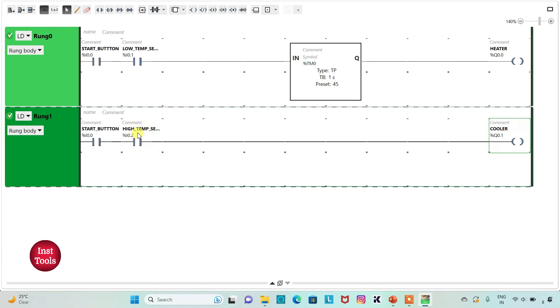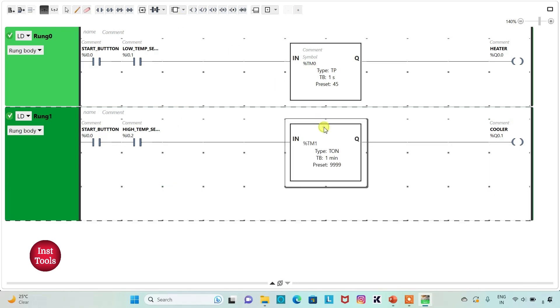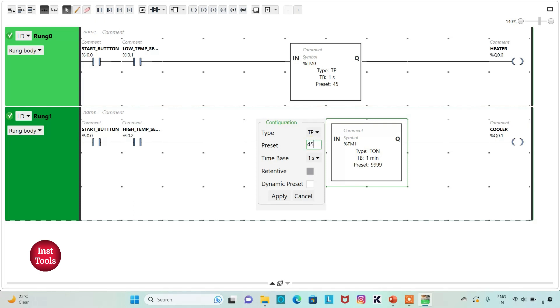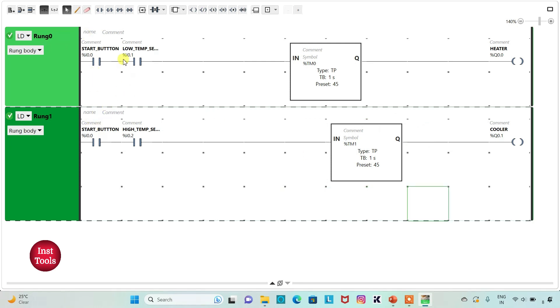When the high temperature sensor senses that the temperature is above 30 degrees, the cooler will be turned on for 45 seconds. I will insert a timer for the cooler — that should be TP — and change the time base to 1 second and preset value to 45, then Apply. So when the start button is on: if the low temperature sensor detects below 25 degrees, the heater runs for 45 seconds; if the high temperature sensor detects above 30 degrees, the cooler runs for 45 seconds.